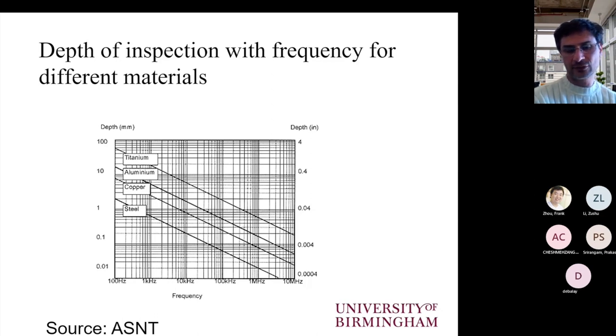Steel, as I said, has the lowest depth of penetration because of the relative magnetic permeability effect. Copper has a bigger depth of inspection, but it is also lower than aluminium and titanium, and this is because of its higher conductivity. And correspondingly, aluminium is the next material that we can inspect in depth for a particular frequency, followed by titanium, which has the lowest conductivity of these three conductors. Steel, as I said, is also ferromagnetic, so it's the ferromagnetic behavior that dominates.